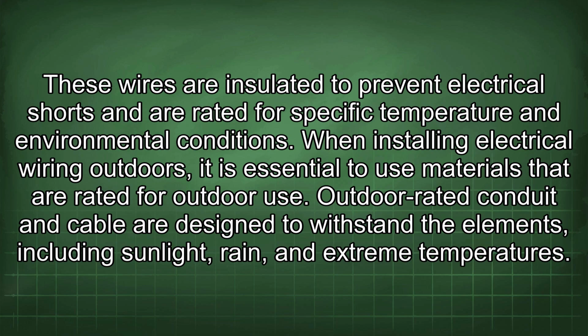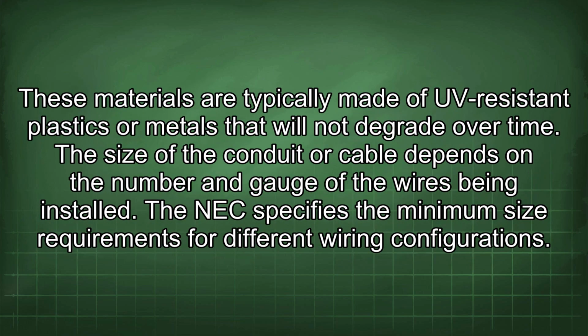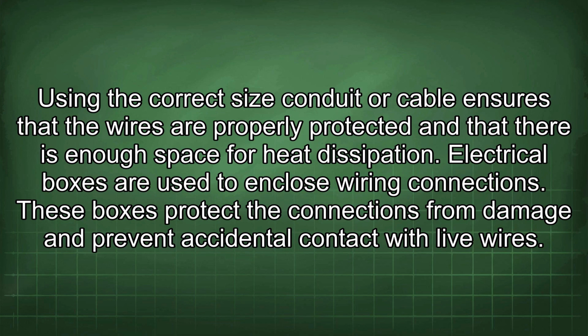When installing electrical wiring outdoors, it is essential to use materials that are rated for outdoor use. Outdoor rated conduit and cable are designed to withstand the elements, including sunlight, rain, and extreme temperatures. These materials are typically made of UV-resistant plastics or metals that will not degrade over time. The size of the conduit or cable depends on the number and gauge of the wires being installed. The NEC specifies the minimum size requirements for different wiring configurations.